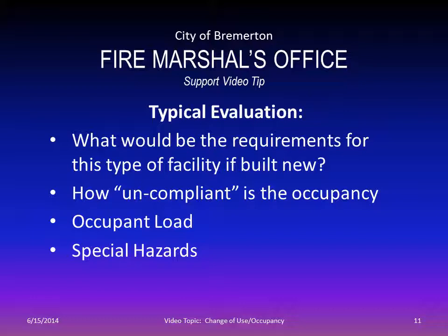So a typical evaluation would be, what would be the requirements if it were built new? This is kind of my process for what I do when I have this type of question. If I have an older existing building and a particular type of business wants to go in, my very first evaluation in my mind is, what would be the requirements if this building were built new? If it were built right now, what would be the requirements? And that's pretty easy to do, really. The codes lay that out pretty easily. Then I'll look at the building. If all those requirements are already in there, fire alarm, fire sprinklers, all those things, you're good, you're golden. There's no hiccup, there's no problem. If some of those things aren't in place, then there's the evaluation.